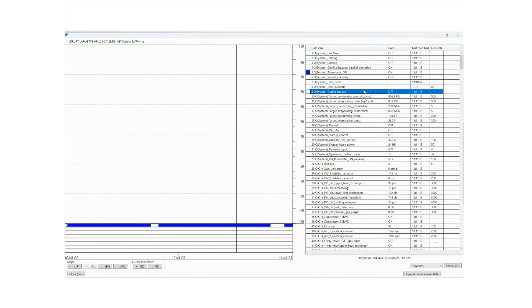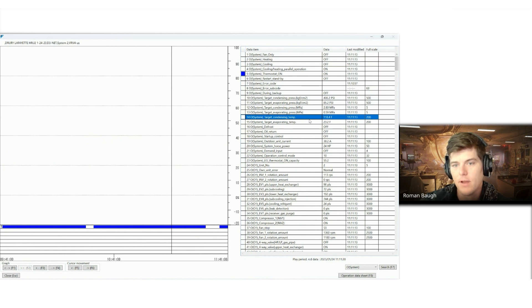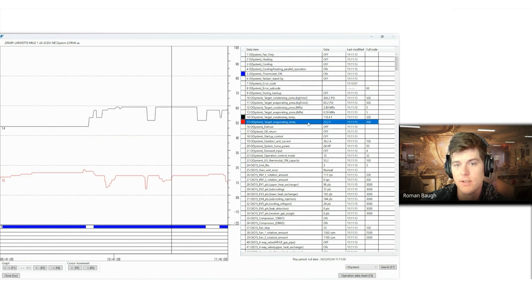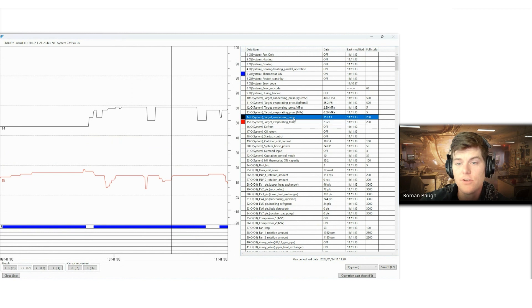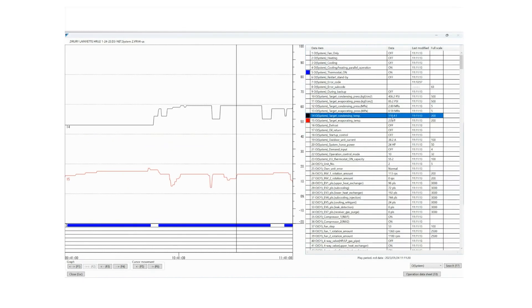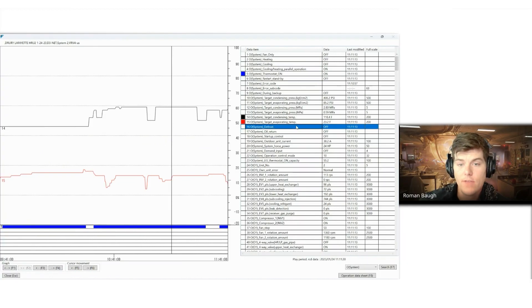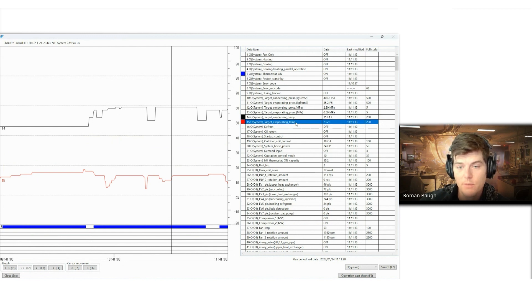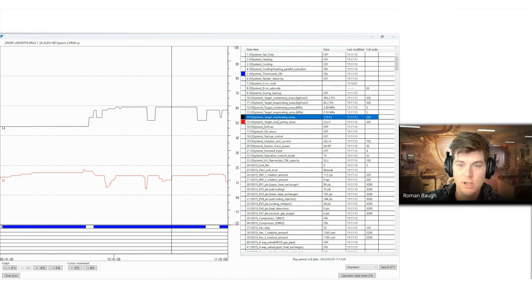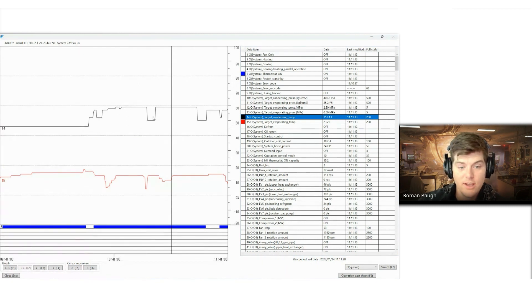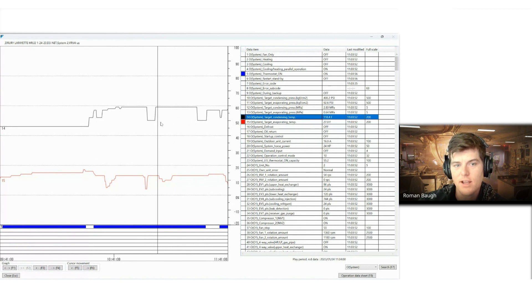Error code, if there is one, sub error code, if there is one. Don't always reference the error codes that are in service checker. Always go to the outdoor unit and verify on the actual board itself. Backup control, target condensing pressure. Then we've got NPA, for those of you who enjoy NPA, target condensing temp. So it gives you the pressure for the target condensing pressure and the target condensing temp. I like to just go off the target condensing temp. But remember, this is what the system is driving to. So when we're talking about looking at service checker data at 118.4, this system is trying to hit 118.4, target condensing temp if it was in a heating mode. If it was in a cooling mode and it's looking for a target evaporating temp of 23.2. And that's important because this is what the system is trying to ramp that compressor up and down to. So if you have an erratic compressor that's going up and down, up and down, you can verify, is my system randomly changing my target condensing temp? Probably not. Yes, you can see here in a two-hour window that it changes, but it's not drastic nor does it happen in a fast manner.